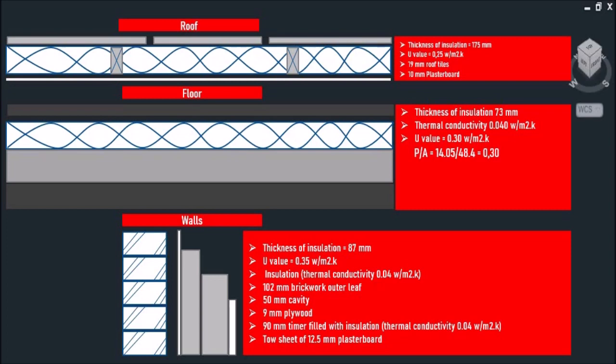As you can see, I have already calculated the required U-value for our roofs, walls, and floors. The thickness of insulation for our roof is 175 millimeters with a U-value of 0.25 watts per square meter Kelvin.